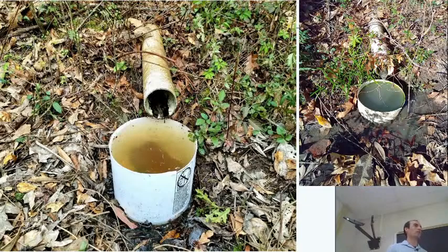It's just not receiving the treatment properly. It might also be the case that because we don't have that biological activity happening in the typical manner, some of the soaps or surfactants aren't getting processed as well and are maybe contributing to the color as well. So definitely sometimes the treatment turns out to be not so good. And again, that should all just be up to the aerator right there.